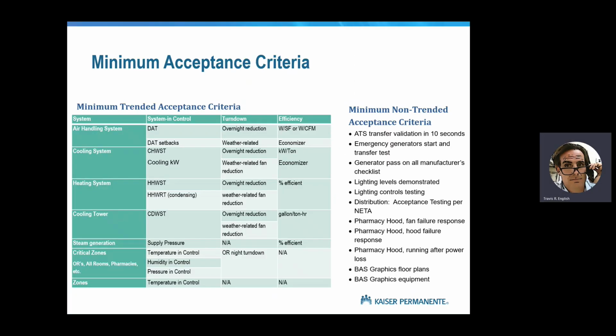And what we started to do about 4 years ago is this. We've started to require acceptance criteria from our design engineers during design. We say to put them on the plans for system validation. What should the data look like on day one when we fire up the system? Put that on the plans where everyone can see it, and we know if it passes or fails during commissioning. And we've discovered that there are about 4 categories of acceptance criteria.